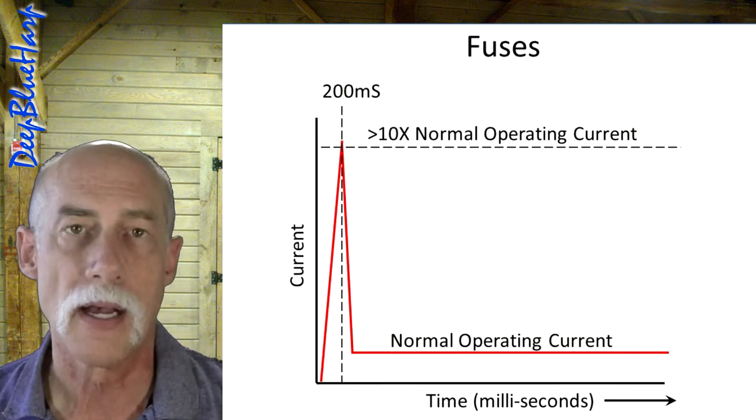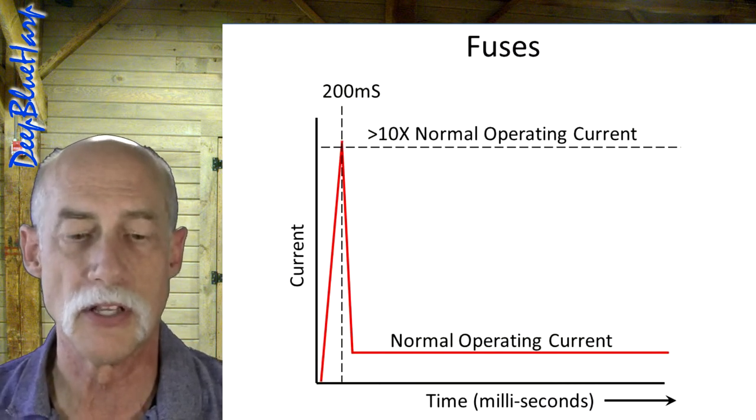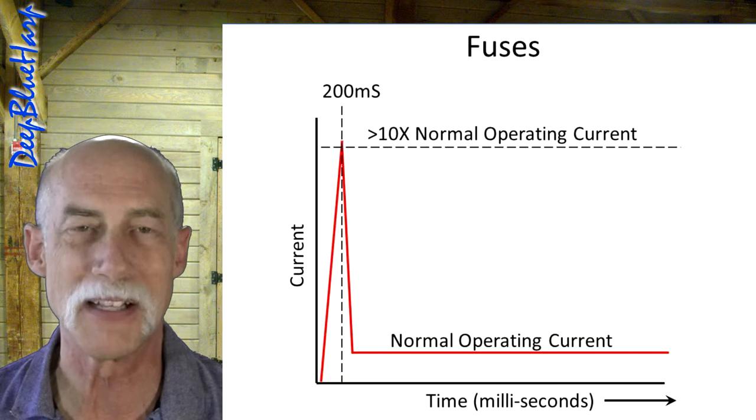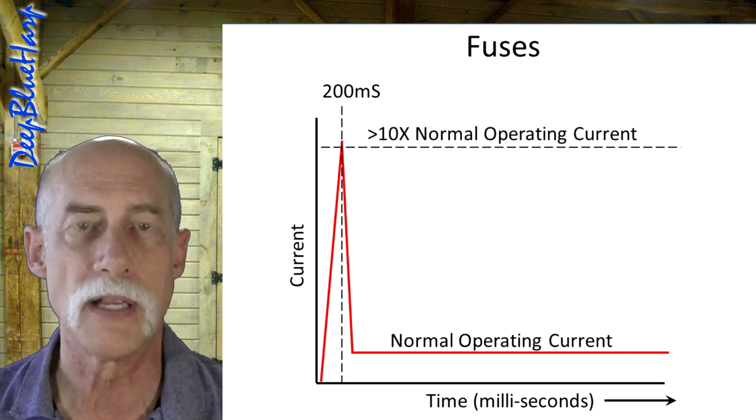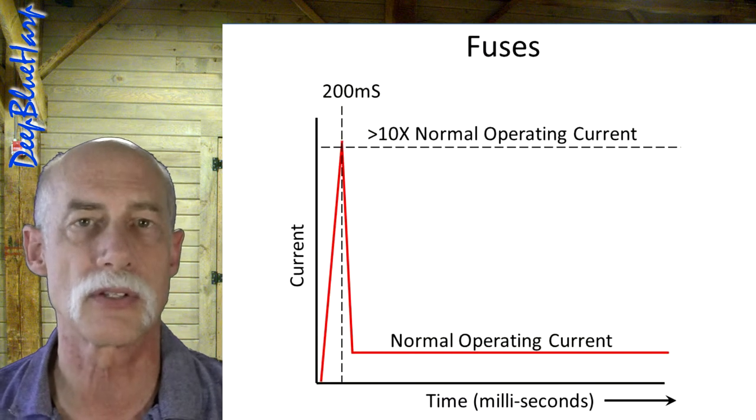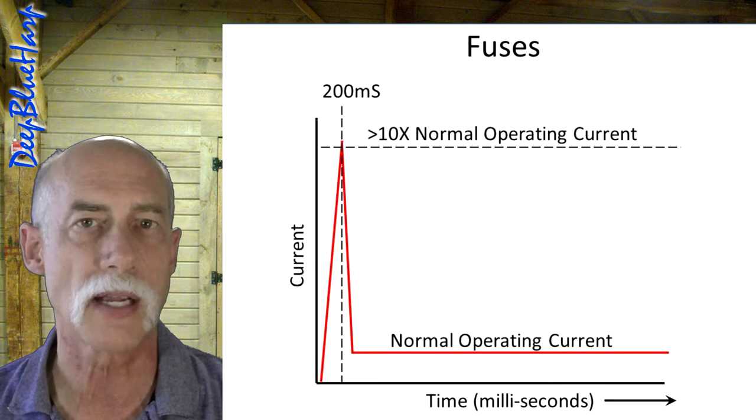A quick blow fuse will not do that. The eutectic point, where it just immediately goes from solid to liquid and breaks, will be instantaneous. So we want something to slow blow. It can actually take the several amps for at least 0.2 seconds.